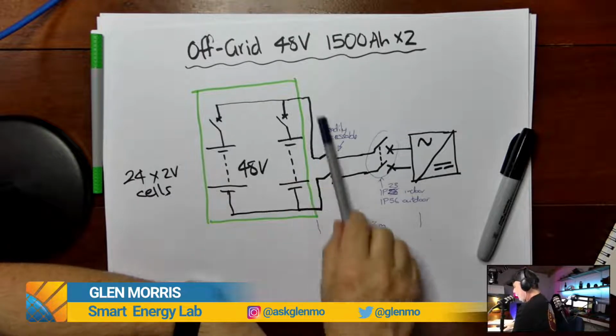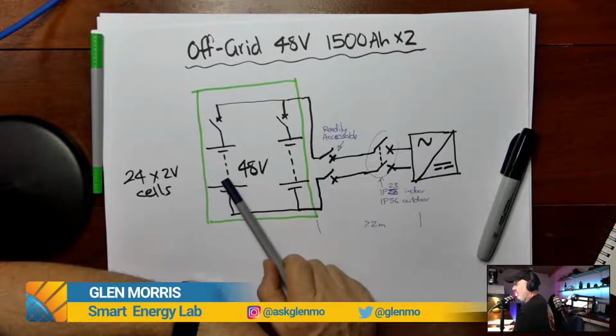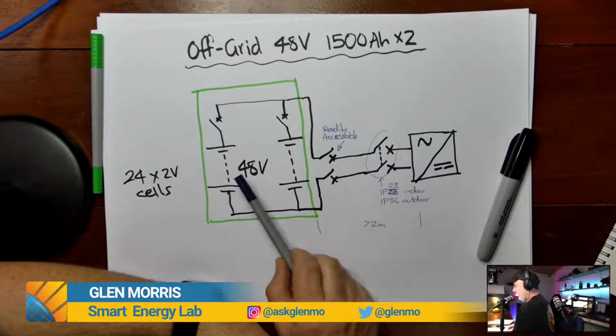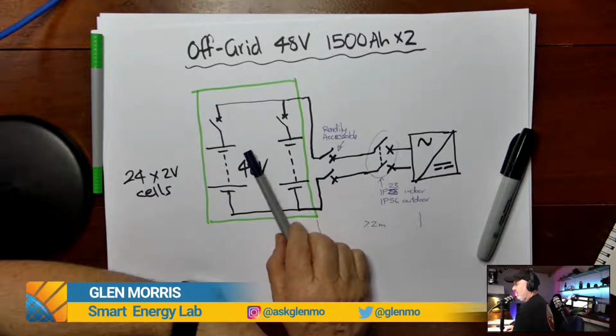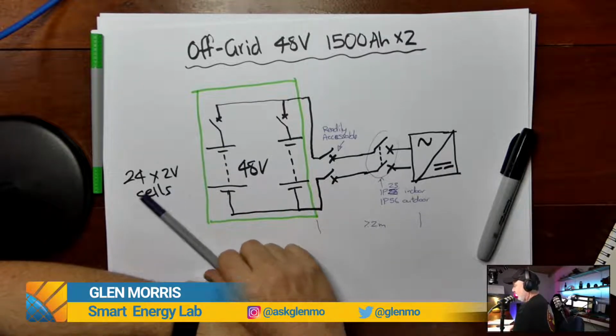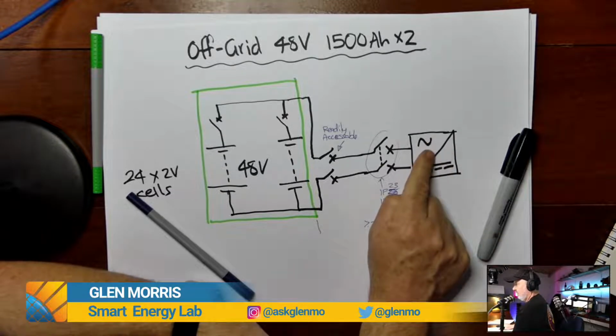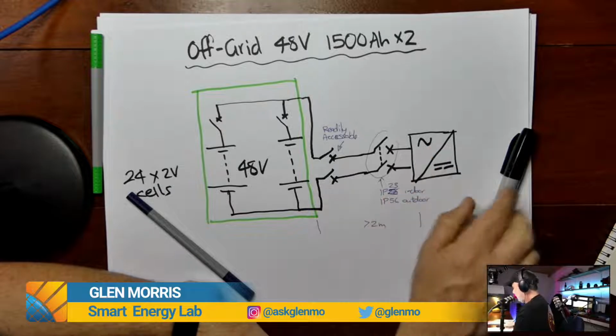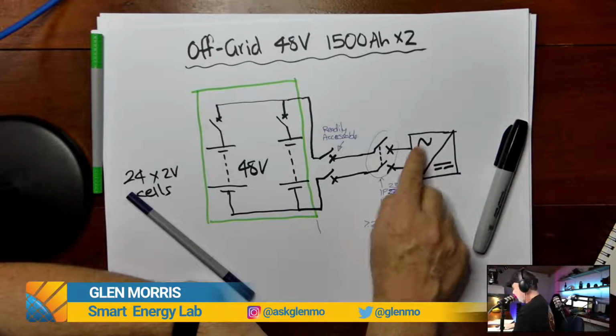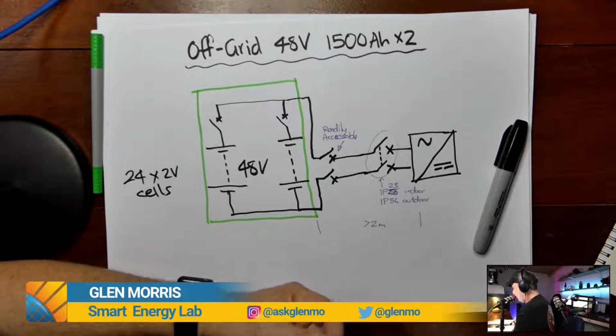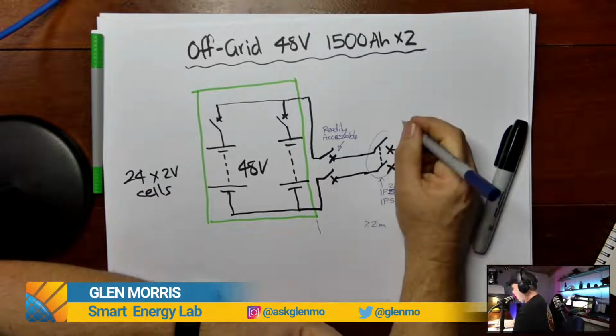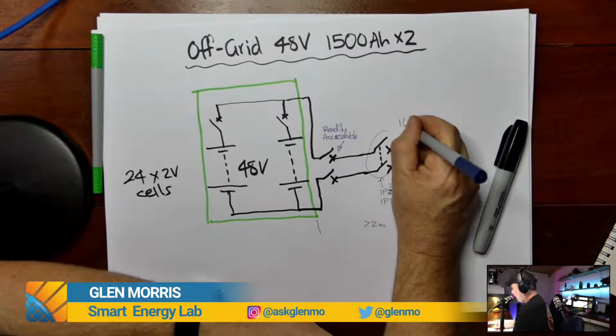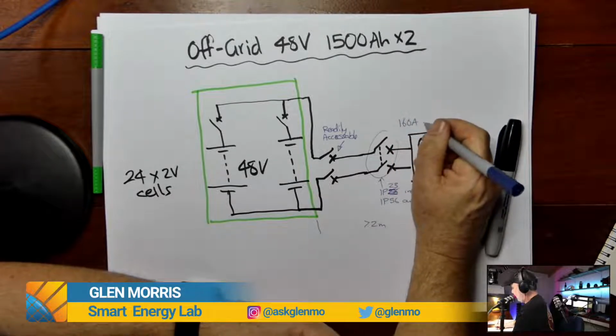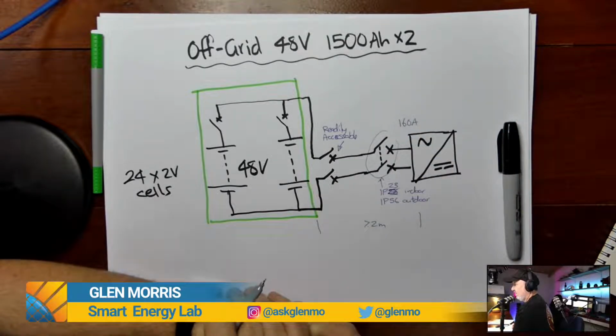So the other thing we need to consider is cable sizing in this design, and also calculate arc flash. Now the cable sizing is based on basically how much you're going to be drawing. So you need to know what the maximum DC current this inverter is going to draw as a continuous rating for this inverter. So let's say this inverter can draw, I don't know, 160 amps. So we've got 160 amps is the maximum current that it's going to draw.